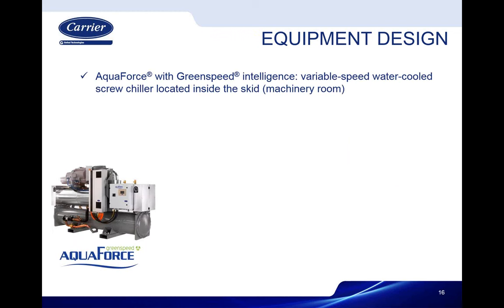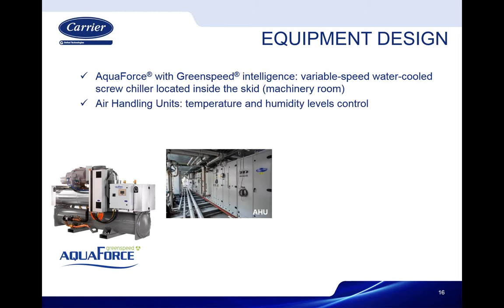We used a screw chiller made in France. It's a heat recovery unit, so we will take the heat on the heat rejection side if we need it for reheat. To achieve the high degree of moisture control, we subcool the air in humid conditions to wring the moisture out, and then bring the temperature back up with reheat using the recovered energy from the compression cycle.